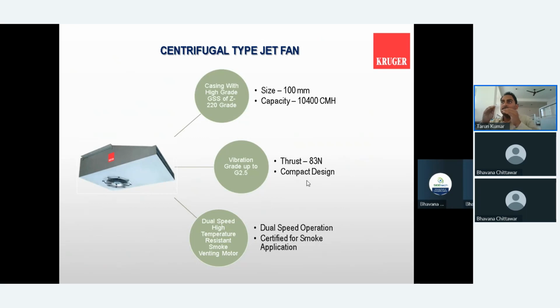And in terms of the coverage area, which is the most important factor for basement ventilation, the centrifugal jet fan has more coverage area compared to the axial jet fan. When you go for any CFD analysis to arrive at the quantity of jet fans, the centrifugal jet fan always needs a lesser number of fans compared to the axial jet fan.